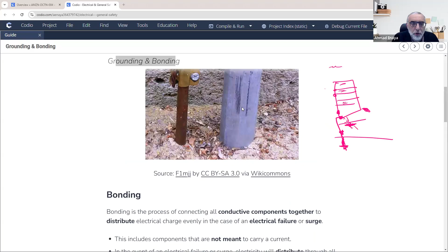Now, in most cases, grounding will be done by a specialized electrician who is authorized or licensed to do the grounding of the building. Your responsibility will be mainly to connect devices to this common ground. So this common ground should be in place already and should be connected to every electrical source, to all the outlets. Your role is to make sure that all devices have three leads or three conductors inside the cable, and one of them goes to this grounding. It is your responsibility to connect the bonding and make sure all devices are connected to the chassis of the rack, and this chassis of the rack is connected to the ground, to the raised floor.